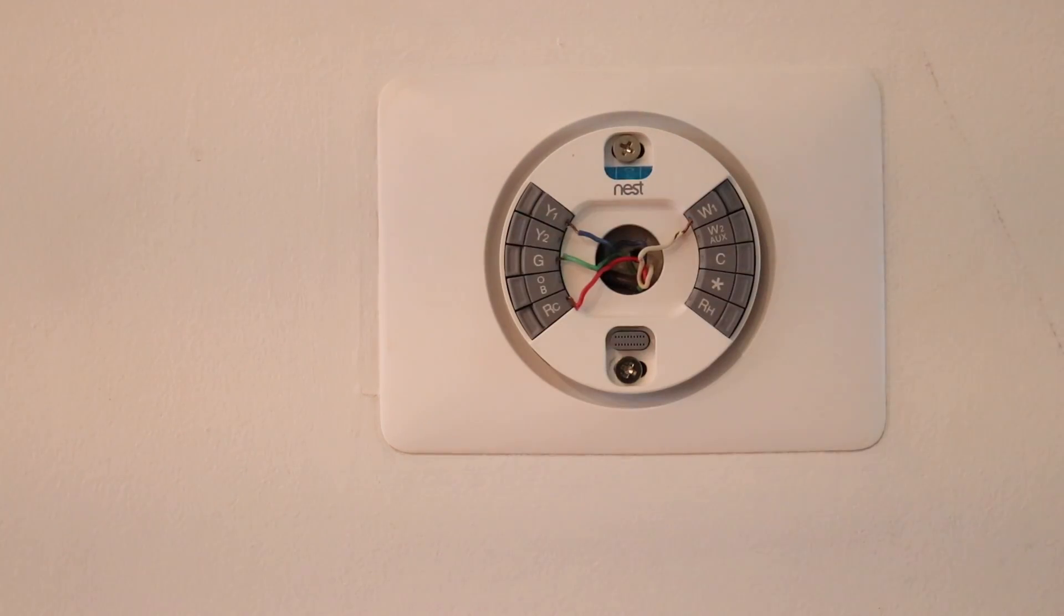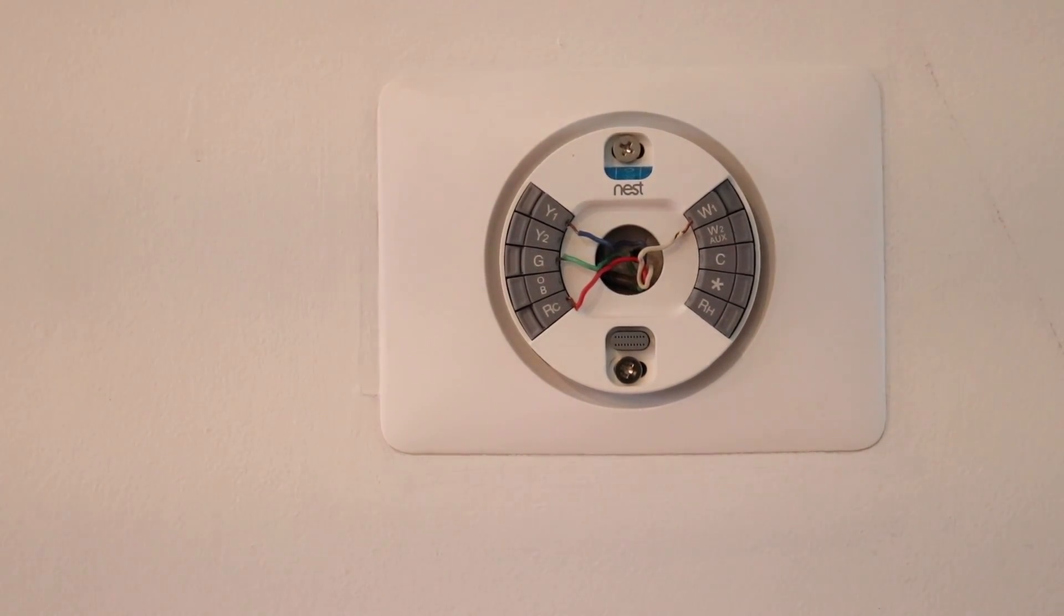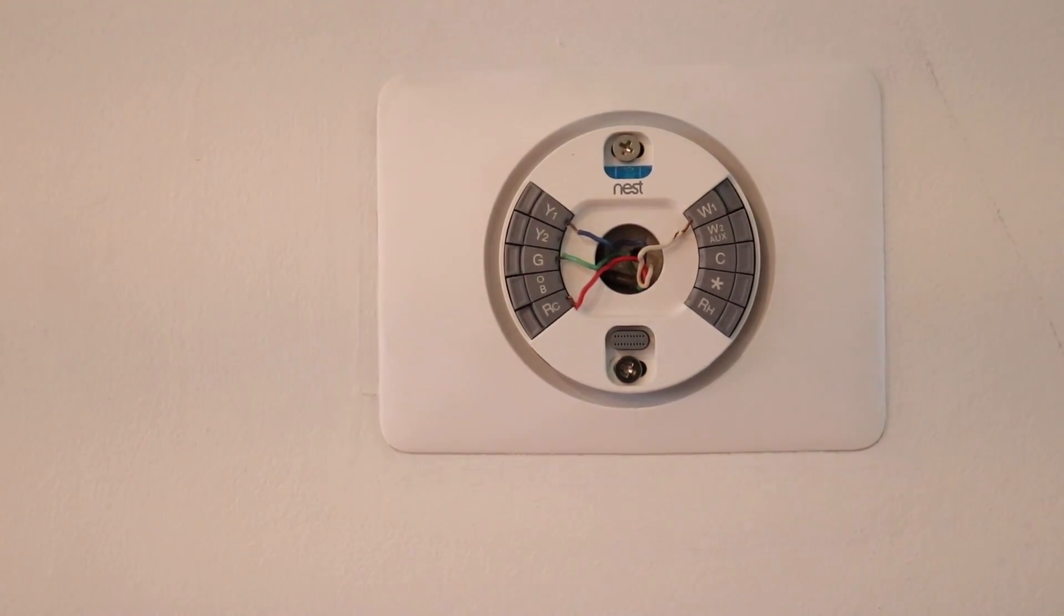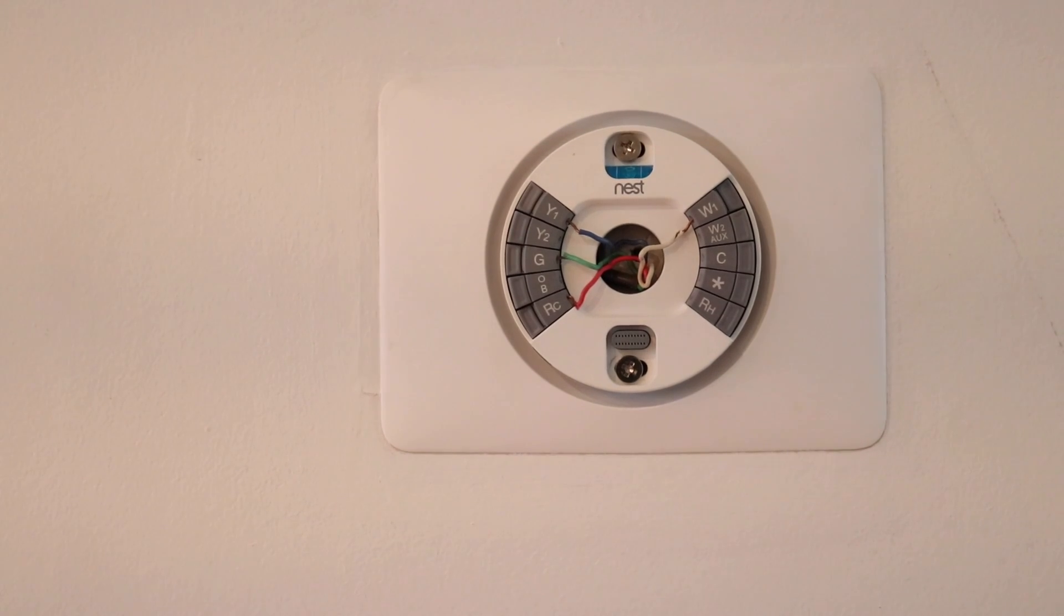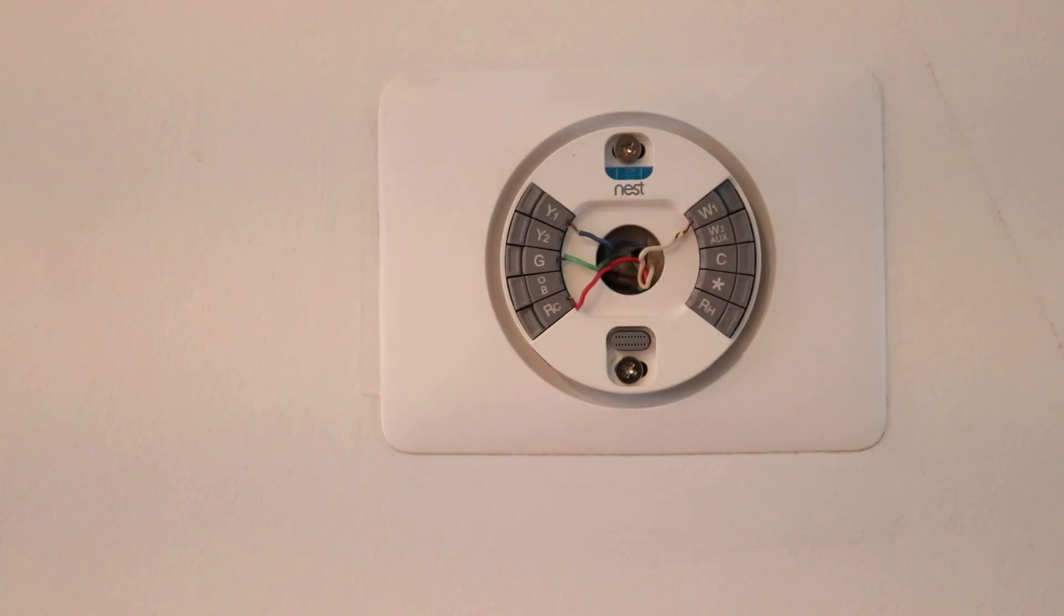The Y1 wire is your cooling and the Y2 wire is second stage cooling. Some newer heating and cooling systems have second stage cooling. And it's just like the one and two stage heating and cooling. For the heat, it's just low power and high power. That's all it is.